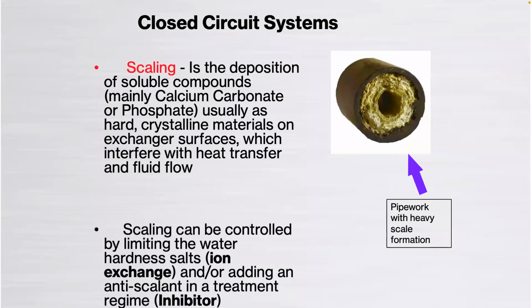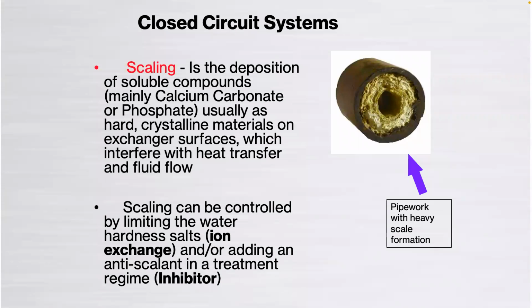So, scale. If you're in a hard water area, when it rains, that water lands on the surface of the ground and, depending on what kind of minerals and rocks are in the ground, that water will absorb them and increase its conductivity and mineral content, typically calcium carbonate or phosphate. Unlike a lot of salts, a lot of minerals, if we heat them up, they like to dissolve. Scale likes to come out of solution. It likes to precipitate as well.